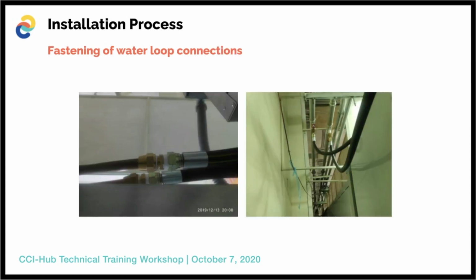Then the fastening of the Waterloop connections. Once the R290 showcase was fixed into position, we connected both the in and out connections of a heavy-duty flexible hose from the pipe gate valve into the heat exchanger of the showcase. The main pipe already had the circulating water and glycol mixture, and these connections must be properly tightened using Teflon tape.